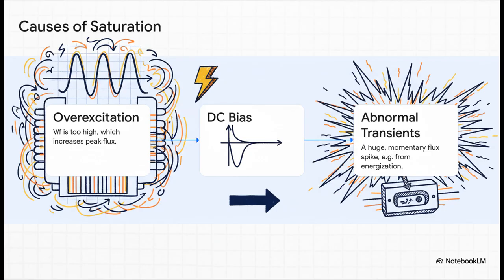Second is a DC bias. This is a sneaky one where a rogue direct current gets in, shifting the whole operation, pushing one half of the AC cycle deep into saturation. And third, you have abnormal transients. Think of the massive surge of current when you first switch a transformer on. It's a momentary shock, but it can cause a colossal flux spike.